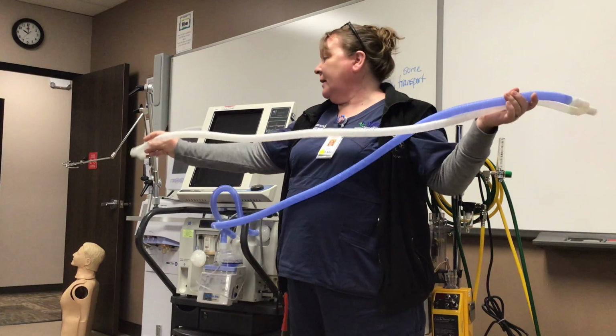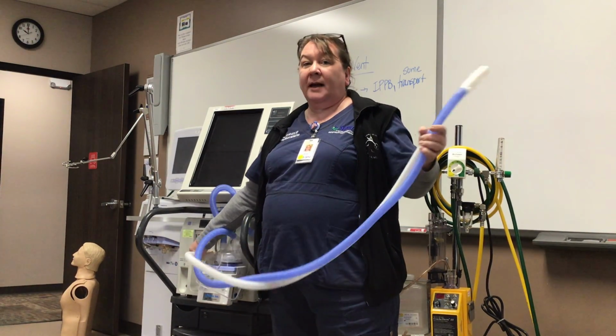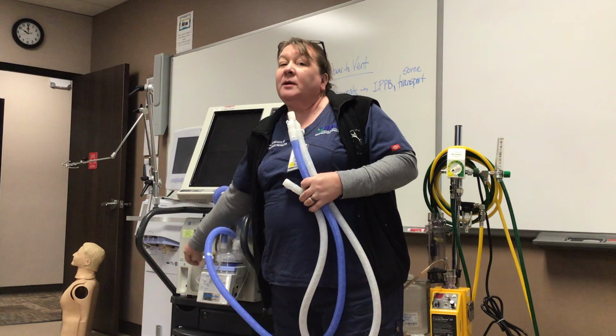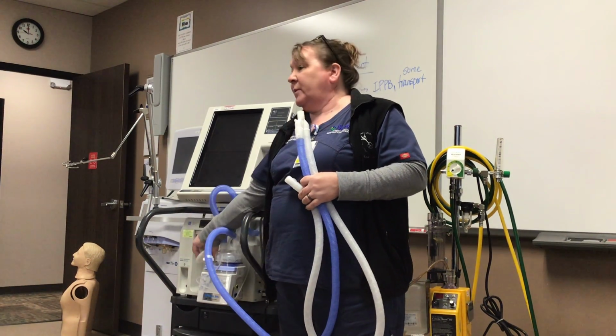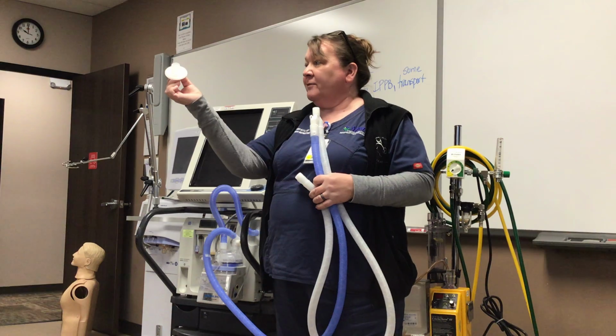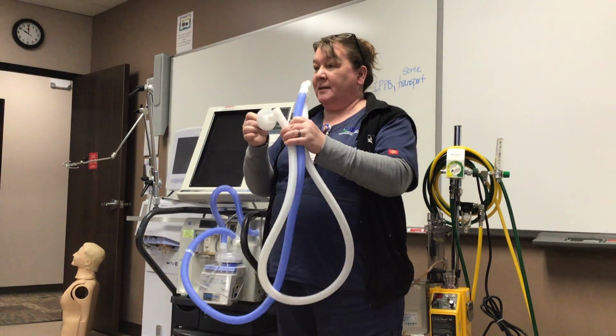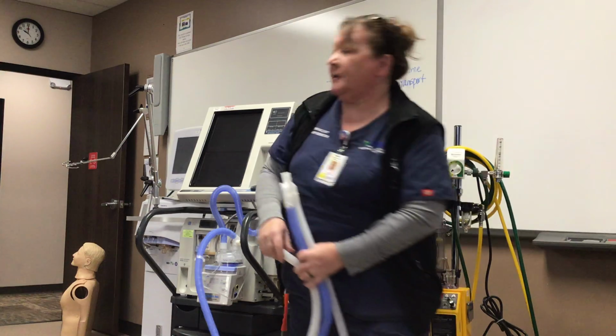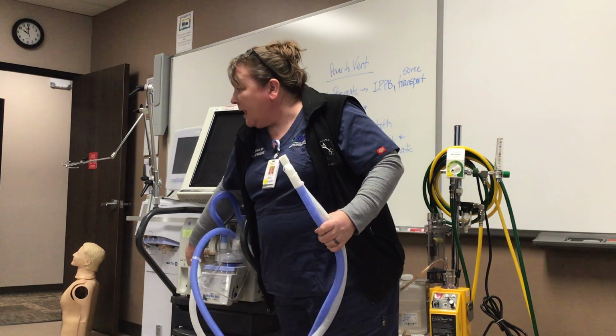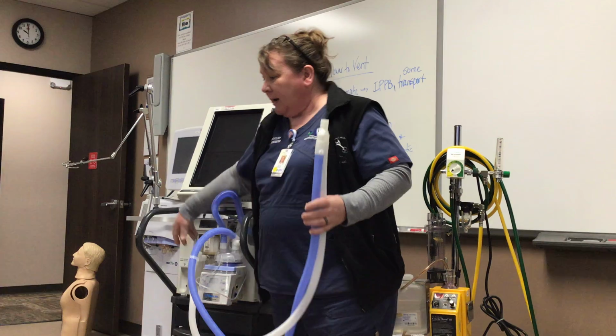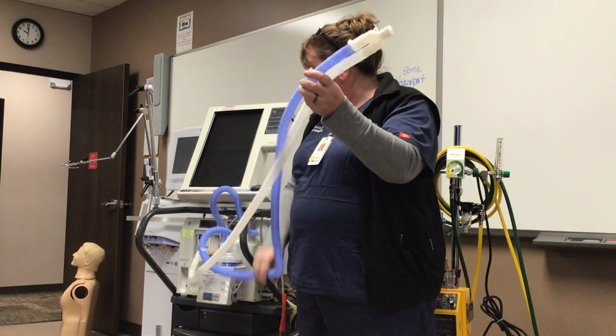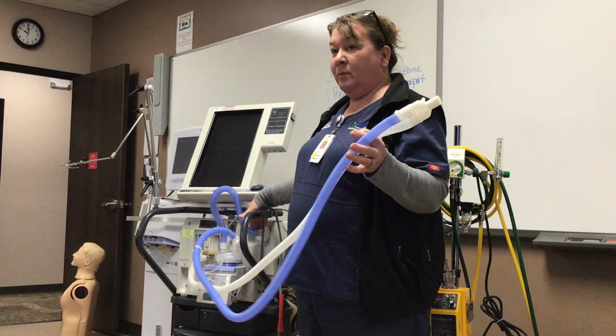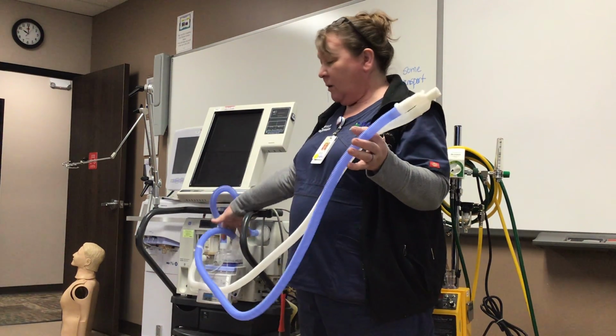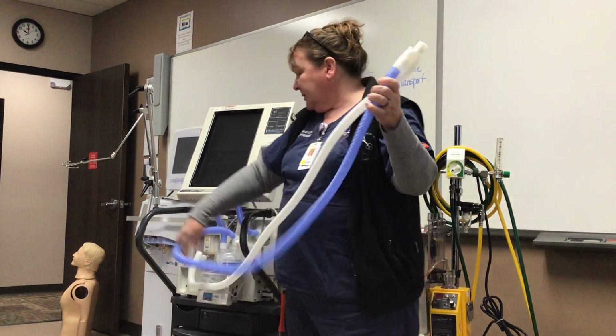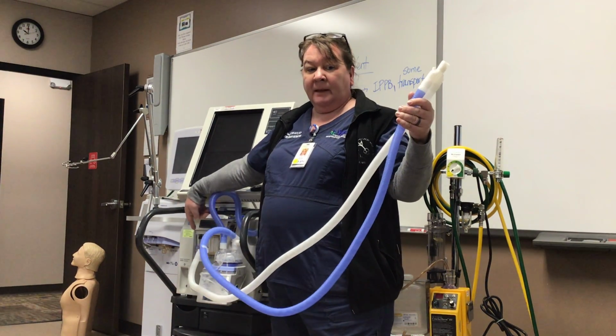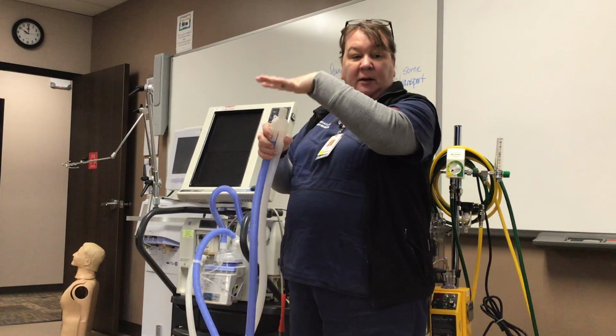So the exhalation side is going to hook to the exhalation side of the PB. And I don't need this filter. The PB, this vent in particular, is the only one that has a built-in exhalation valve. So every other vent, you would put this on it and then hook your circuit to that. So this one here is going to go right here. And I will do a separate demo on each ventilator once we get past the beginning here. So now I've hooked air from the ventilator to the water, from the water to the patient, and then air going back, exhalation, into the exhalation side. And then you can put your Ballard or whatever else you need on here depending on what you're doing.